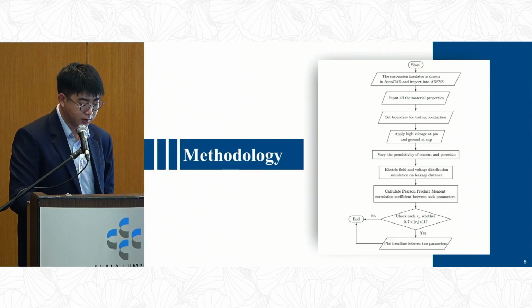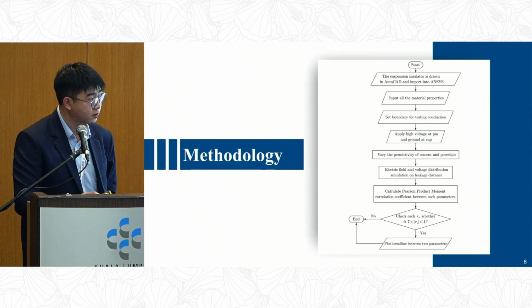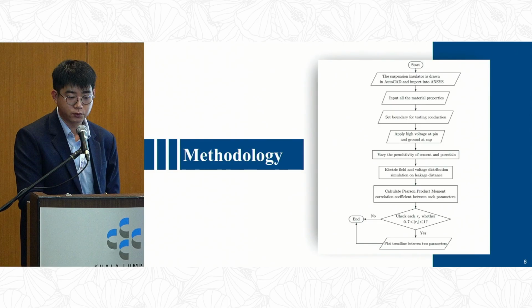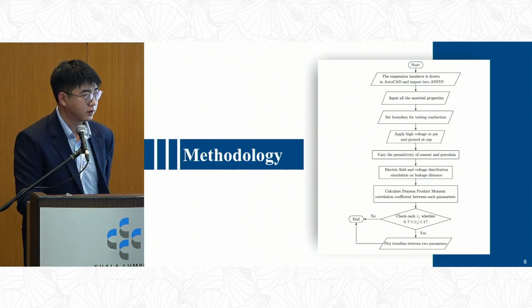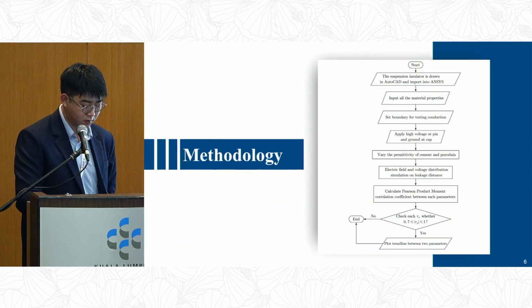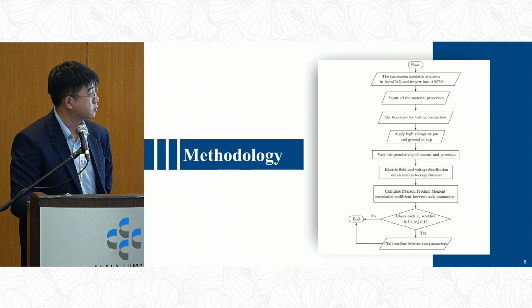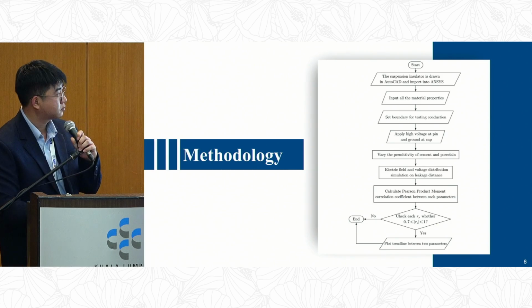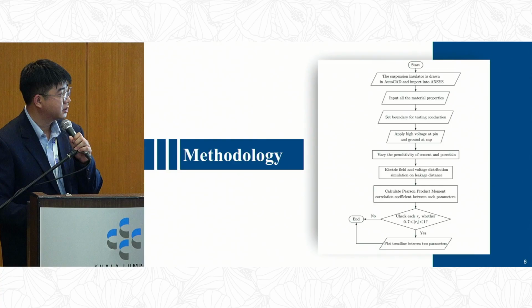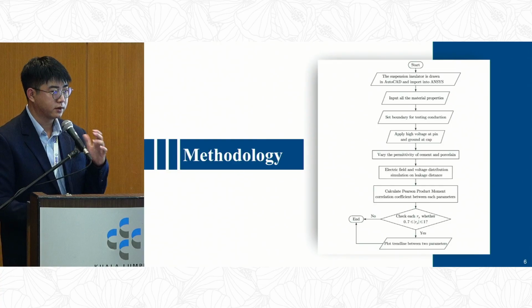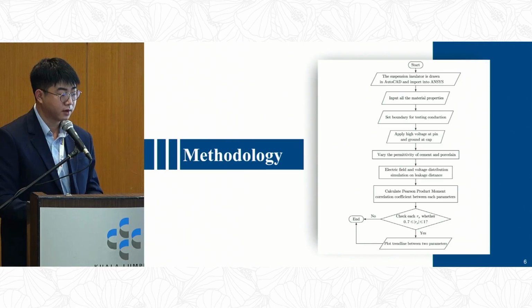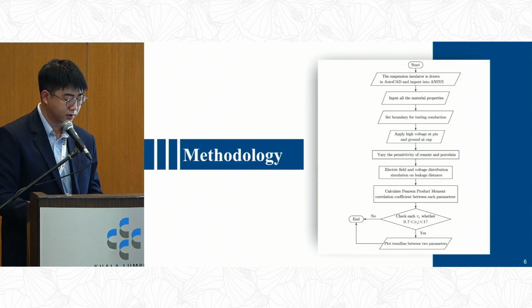As in a real insulator system, the pin will be applied with a high voltage of around 10 kilovolts, and the cap will be grounded at 0 volts. After that, we will change the permittivity of the cement and the porcelain in order to see the difference between the electrical field and voltage distribution.